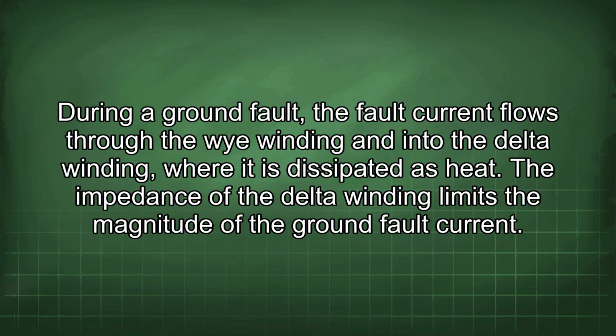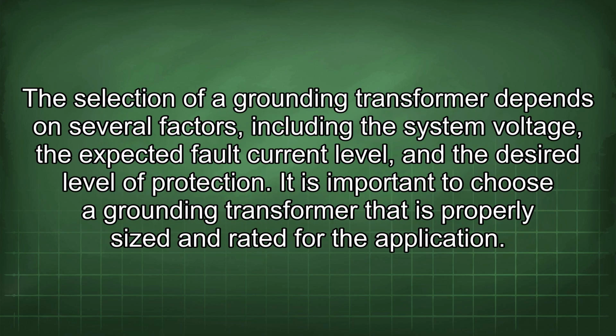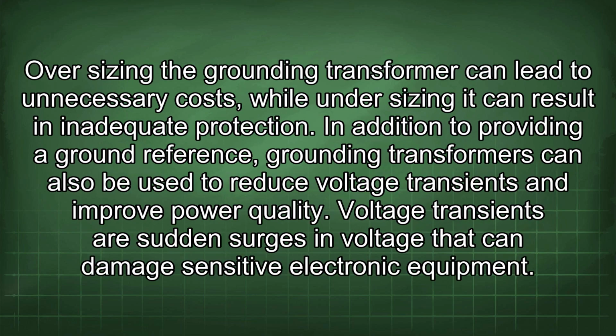During a ground fault, the fault current flows through the Y winding and into the delta winding, where it is dissipated as heat. The impedance of the delta winding limits the magnitude of the ground fault current. The selection of a grounding transformer depends on several factors, including the system voltage, the expected fault current level, and the desired level of protection. It is important to choose a grounding transformer that is properly sized and rated for the application. Oversizing the grounding transformer can lead to unnecessary costs, while undersizing it can result in inadequate protection.